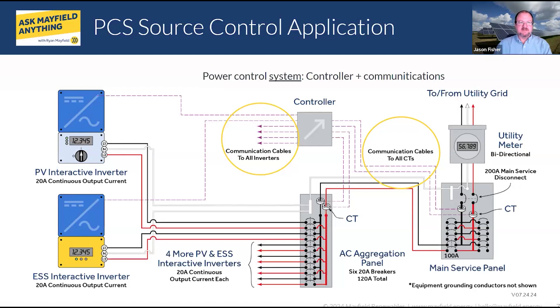The really key part about thinking of this as a system is that it is a system evaluation and a system listing. In this case, it would also include these inverters, because the inverters must also have gone through that same evaluation — for example, what if you're signaling the inverter and it doesn't respond? What does the controller do? What does the inverter do? Communication, coordination, and reliability are all really critical with regards to the power control system evaluation.